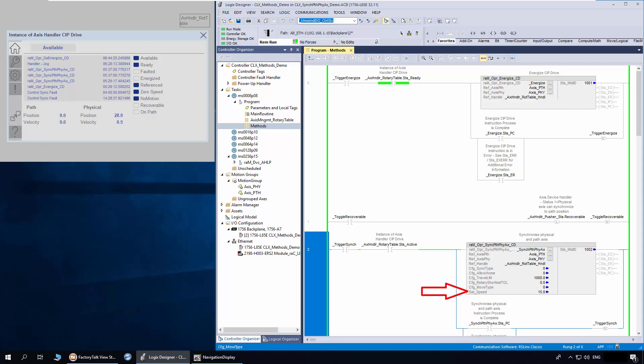Set speed is the physical axis speed during recovery movement. After controller power recycle or program to run mode, the status recoverable bit is reset by the handler. This is to prevent physical to path axis recovery, as path axis position gets reset after controller power recycle or program to run mode changeover.